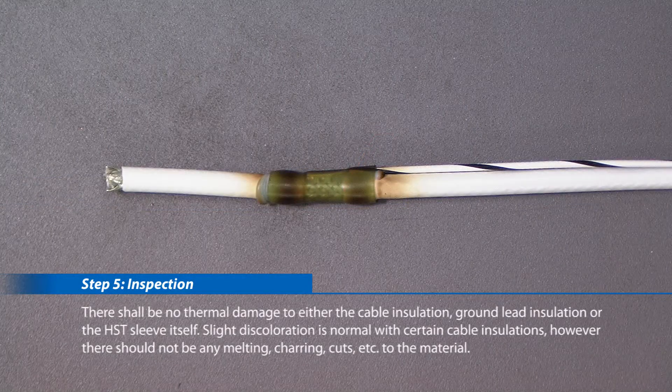There shall be no thermal damage to either the cable insulation, ground lead insulation, or the HST sleeve itself. Slight discoloration is normal with certain cable insulations; however, there should not be any melting, charring, cuts, etc. to the material. Take care.